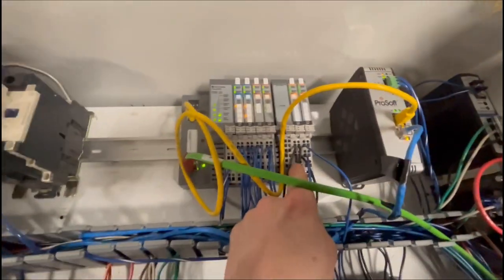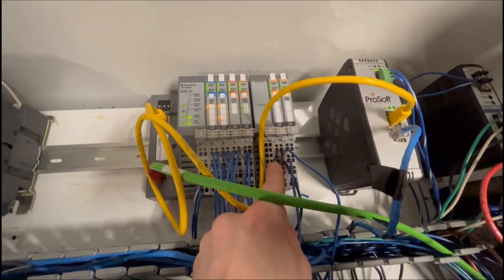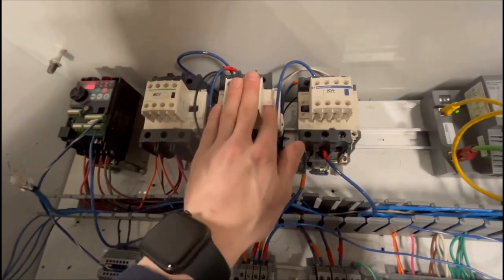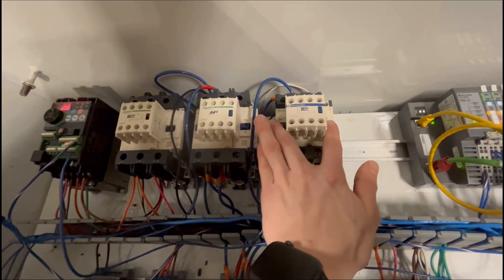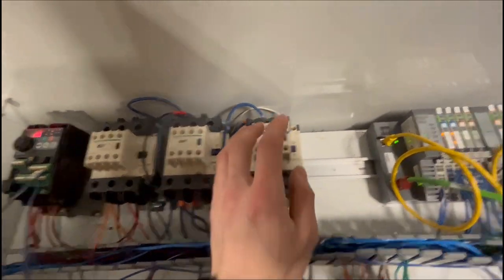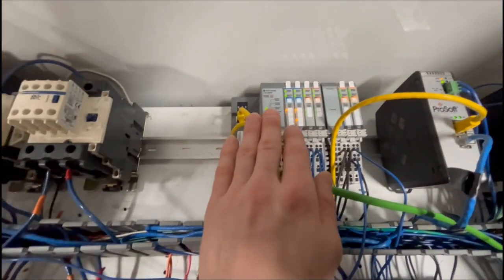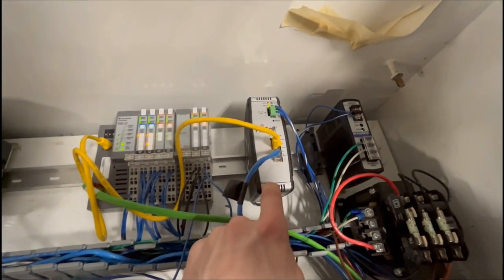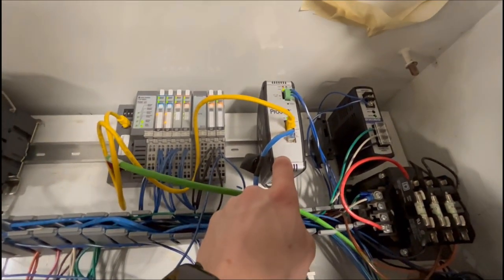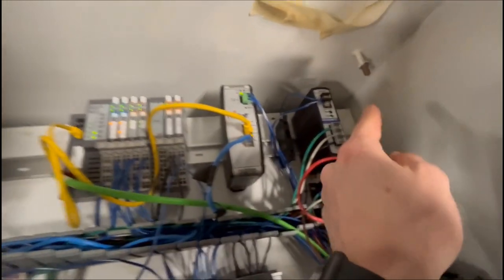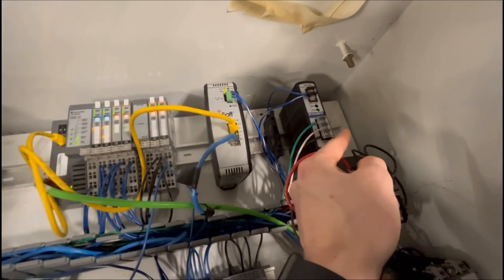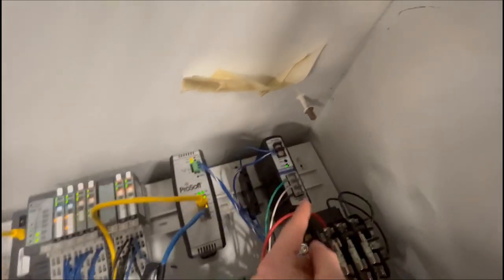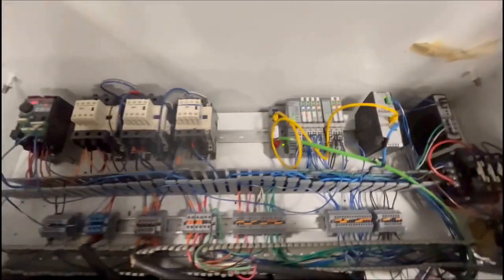Then we have all these black wires coming out of this relay output card, powers these 2 contactors for the heaters. Then we just have this point IO, this ProSoft Ethernet to Modbus converter I ended up not using because I couldn't figure out Modbus. This is just our DC power supply, and that's about it. We don't have many components here. It's all pretty simple, but that's it for the components in this panel.